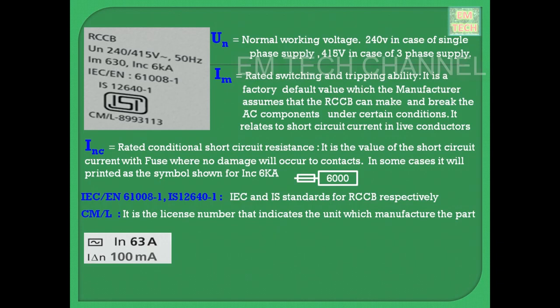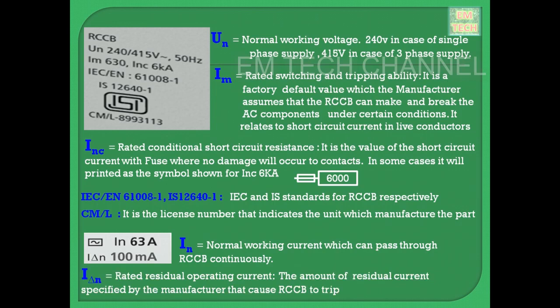You can see in the left corner the load characteristic symbols as we saw before, and it indicates a type AC RCCB. IN is the normal working current. It is the rated current that can pass through the RCCB continuously, and I delta N is the rated residual operating current, meaning the leakage current, and it is the amount of residual current specified by the manufacturer above which the RCCB will trip. Okay guys, we came to the end of this session.